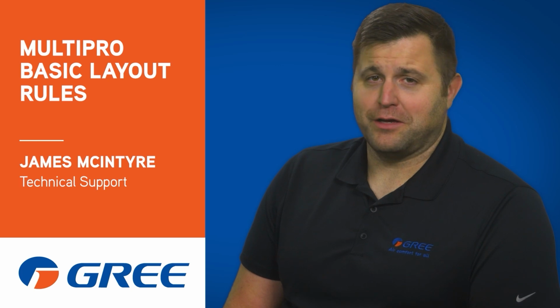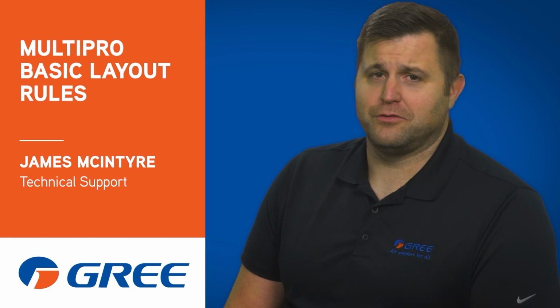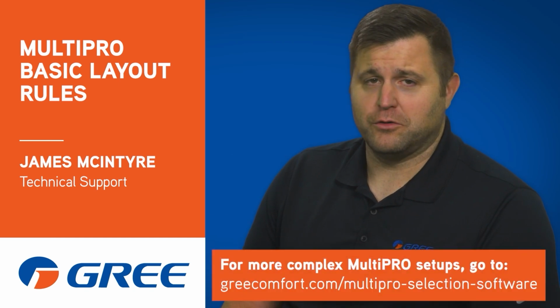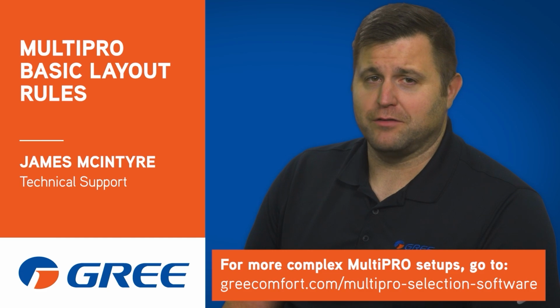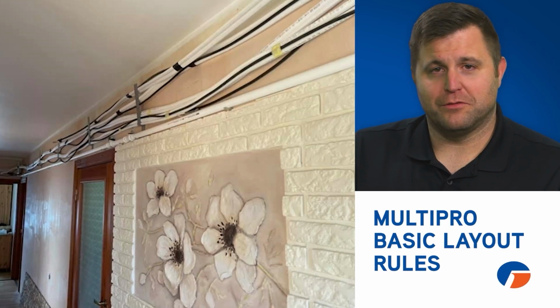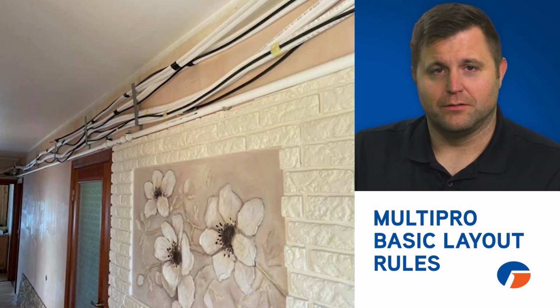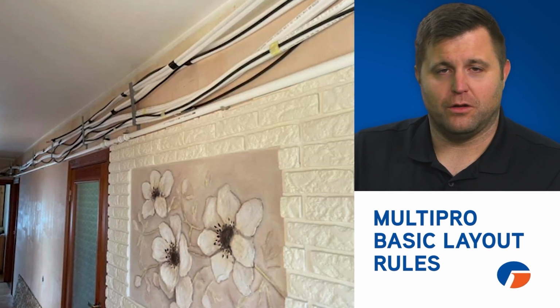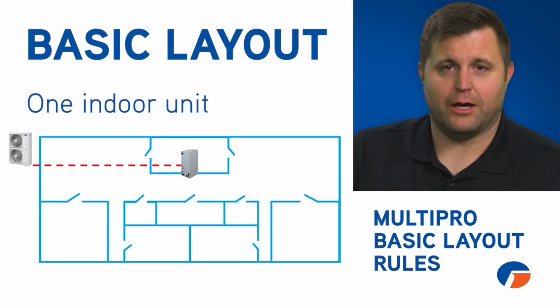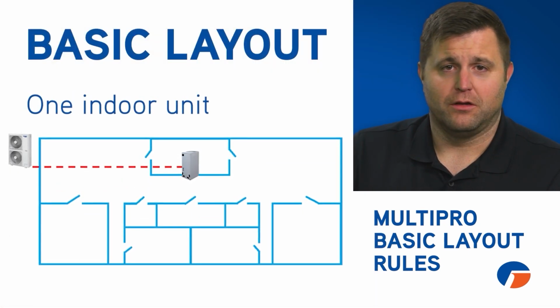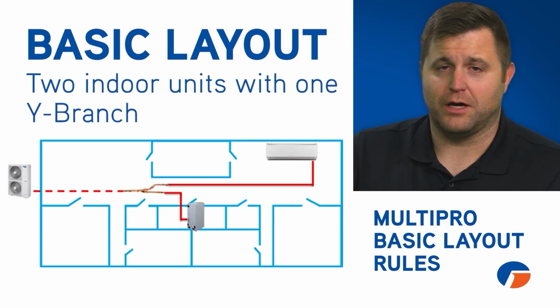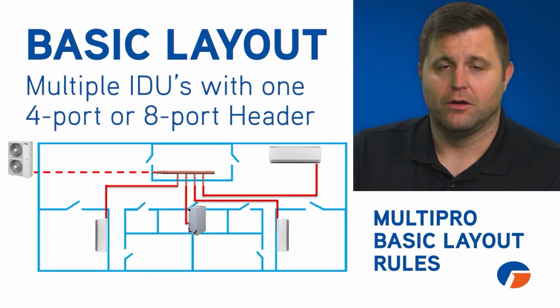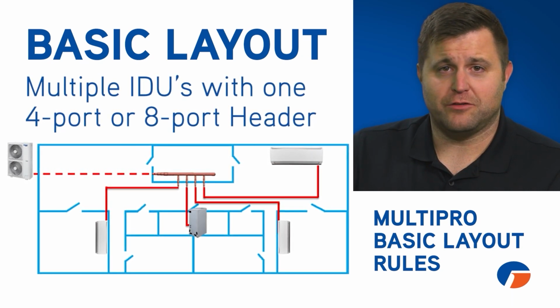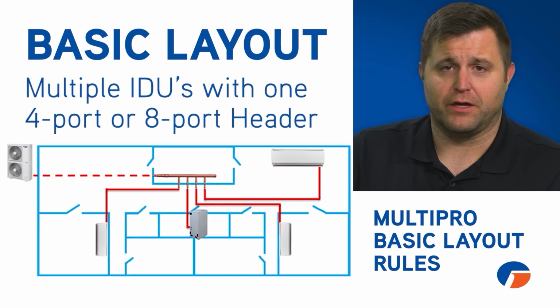Here at GREE, we all like making things as simple as possible. MultiPRO systems can utilize up to 10 indoor units and hundreds of feet of piping, and we have software called MultiPRO Selector available at GreeComfort.com that makes that pretty easy. However, most systems will have a simpler layout and much shorter piping. So we have developed a tool we're calling the basic layout. A basic layout is a system that has only one indoor unit, a system using 2 indoor units connected by a Y branch, or a system using 3 to 8 indoor units using only one 4-port header or an 8-port header. The vast majority of MultiPRO systems will have this simplified layout.